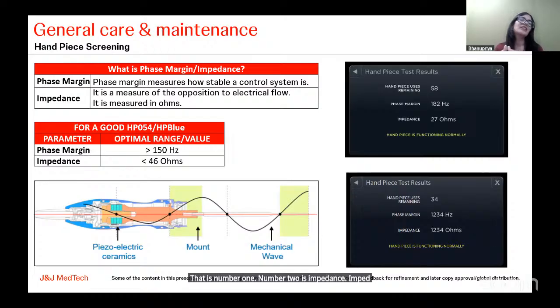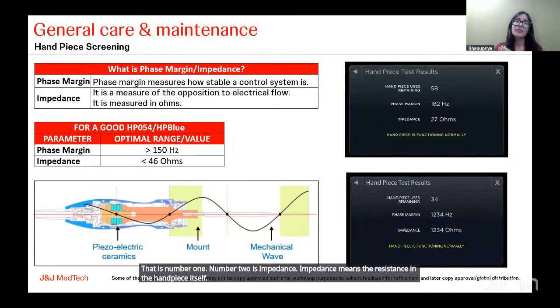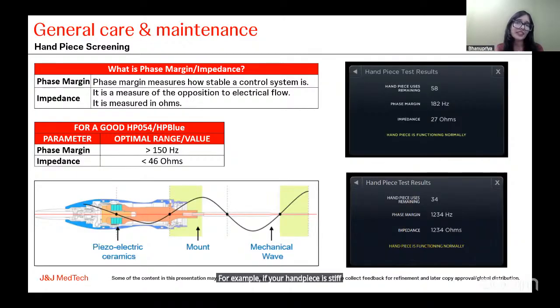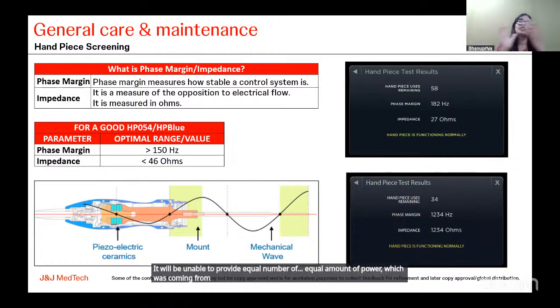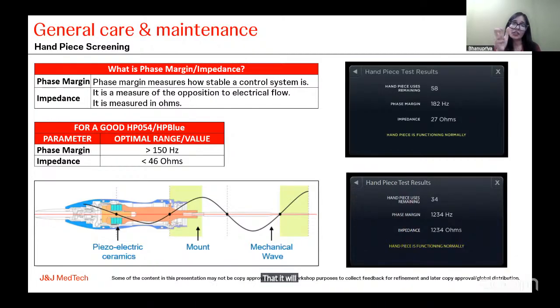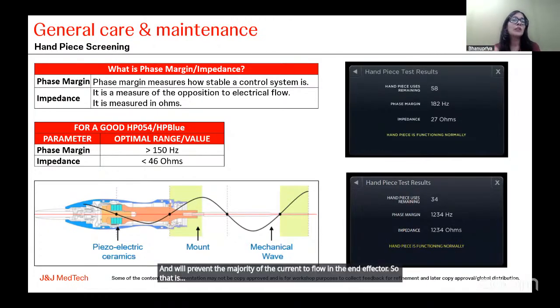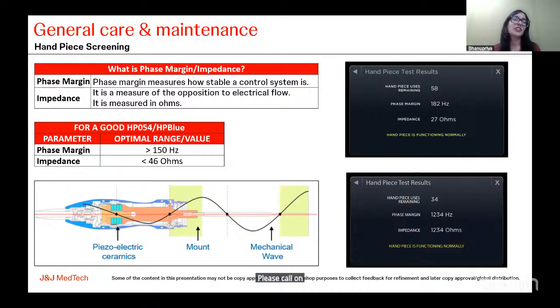Impedance means the resistance in the handpiece itself. For example, if your handpiece is stiff, it has more resistance in itself, and it will be unable to provide an equal amount of power from the generator to the probe. Your handpiece itself has so much resistance that it will suck away the majority of the current and prevent the majority of the current from flowing into the end effector. So that is a system inbuilt process. The system will check your handpiece for itself, and if you still feel that the handpiece is not working, please call a J&J sales representative or a field service engineer.